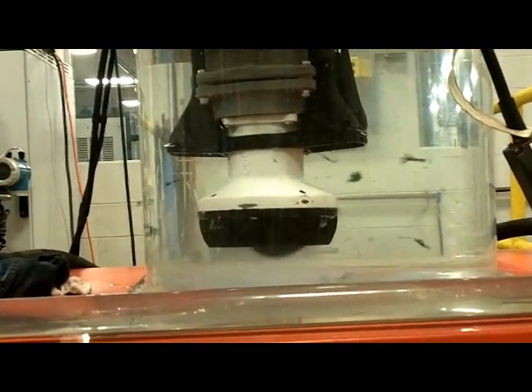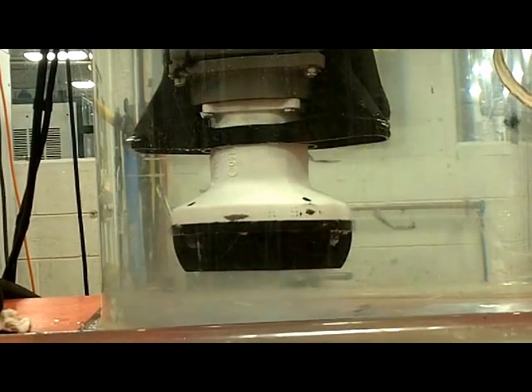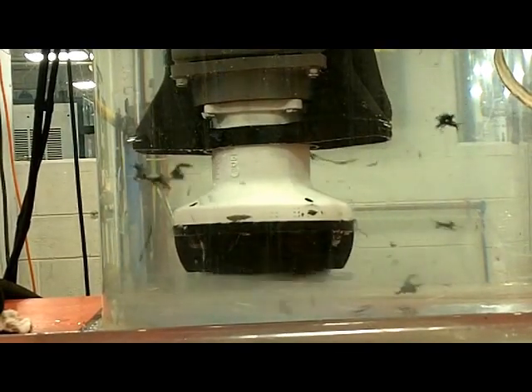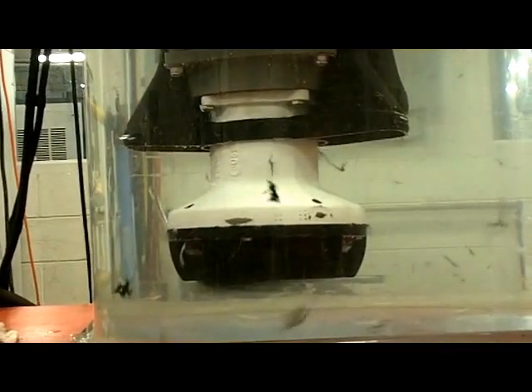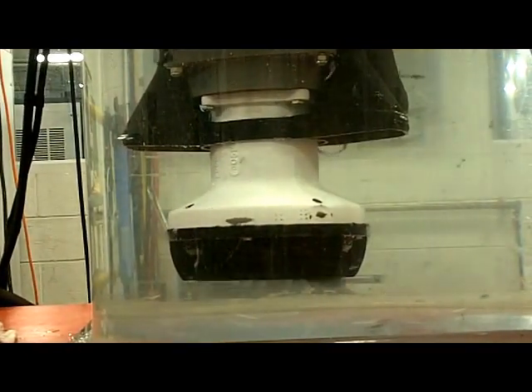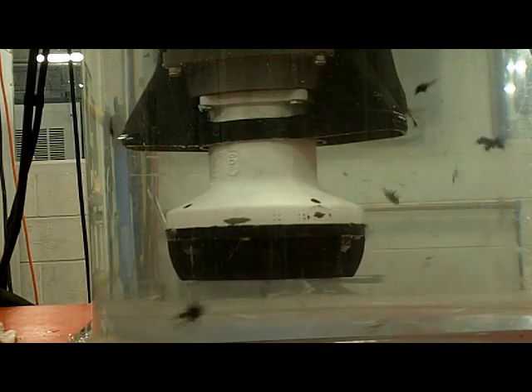The function of the grinder is to reduce the size of everything in raw wastewater into particles small enough to pass freely through inch and a quarter pressure laterals. In practice, most solids that have been through the E/One grinder pump will measure between one quarter inch and one half inch.